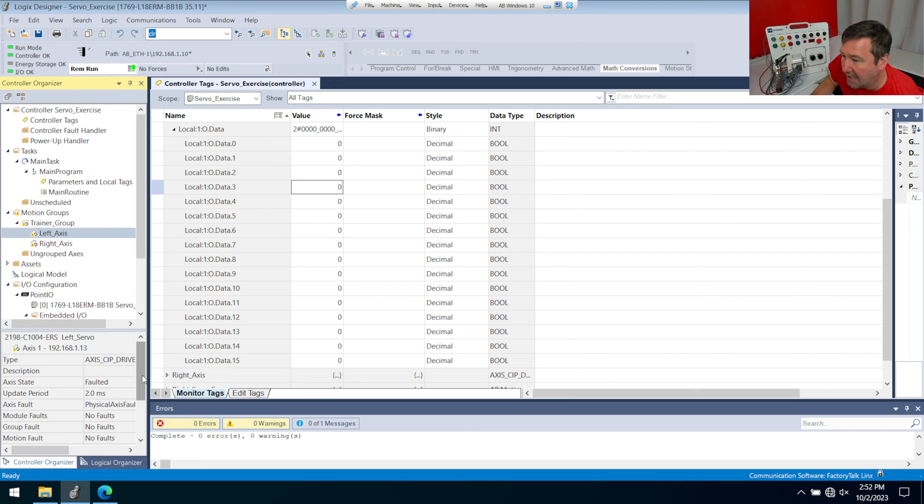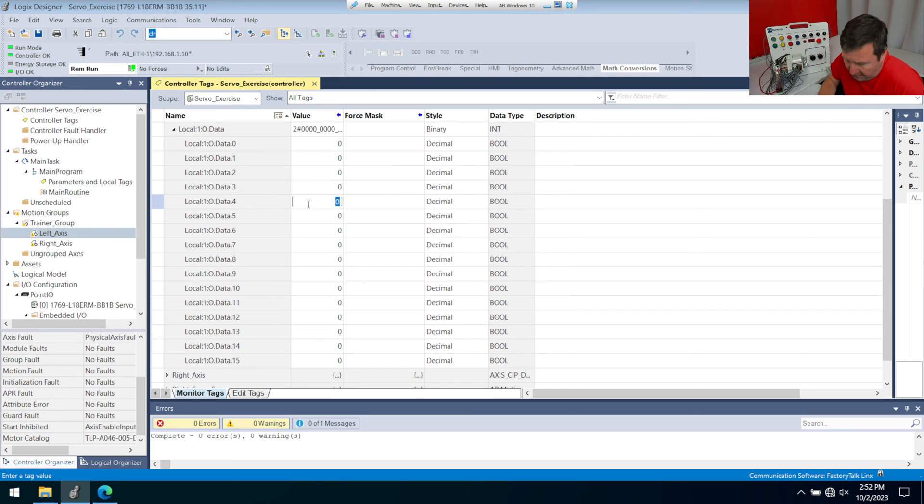I'm going to click the left axis, and I can go down and there's our axis enable input inhibit. Right now that's keeping us from starting. We're going to put a one in output four, and that tells us it's not inhibited, which means our enable signal is good. Then we'll take the right axis and we're going to put a one in output five, and now its axis is not inhibited.